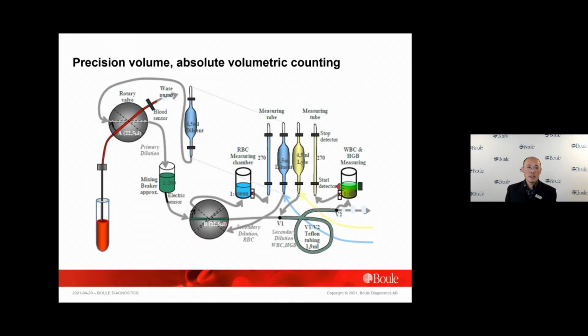So let's see the hardware. In this schematic drawing, you see the shear valve, which takes a precise volume measure of the whole blood and then makes a dilution into the mixing beaker. So here it is the first dilution for all the parameters, preparing for the second dilution. For the second dilution, the diluted blood also passes the shear valve, another channel inside the shear valve, to measure a precise volume for the RBC and platelet measurement. While inside the instrument, there is a fixed length tubing with exact volume to measure the volume of first diluted blood, preparing for the WBC second dilution.